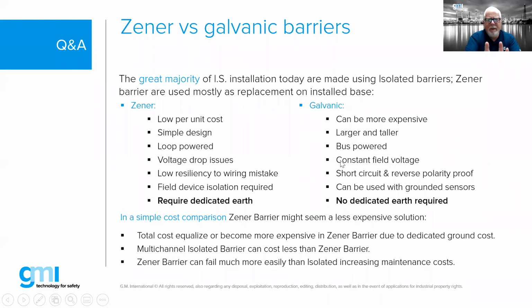Galvanic is safer. Again, the big issue is the no dedicated earth. But when we talk about cost comparison, Zener barriers typically were less expensive. However, when we start adding in the cost of all the other things, we can find that Zener barriers are a lot more expensive. Also, Zener barriers, because they are directly connected to the power source, have a tendency to blow the fuse during startup. This happens an awful lot. Because galvanically isolated barriers seem to be a little bit more robust and can handle that, that's one benefit you'll find. It's not necessarily obvious to a lot of people—galvanically isolated barriers typically are going to be better during that startup process.